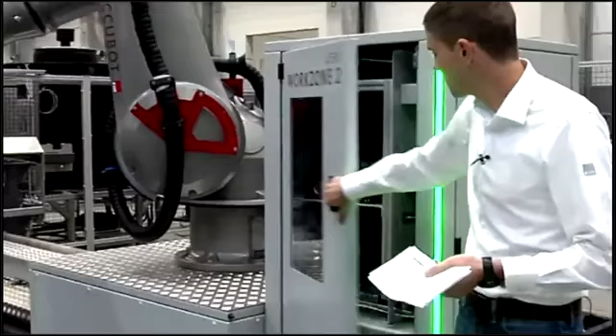Okay, now I would like to go into more detail about our ultrasonic solution. The small red box, which is visible here, is our UT electronics. It's from our partner and supplier Force Technology from Denmark, and it provides 8 high dynamic single channel ultrasonic channels and is able to perform phased array inspection as well. For through transmission inspection, the single channels provide very high dynamics. So with 1 megahertz, we can reach up to 120 dB usable dynamic, and with 5 megahertz, it goes up to 115 dB, which is quite much, especially for high damping materials.